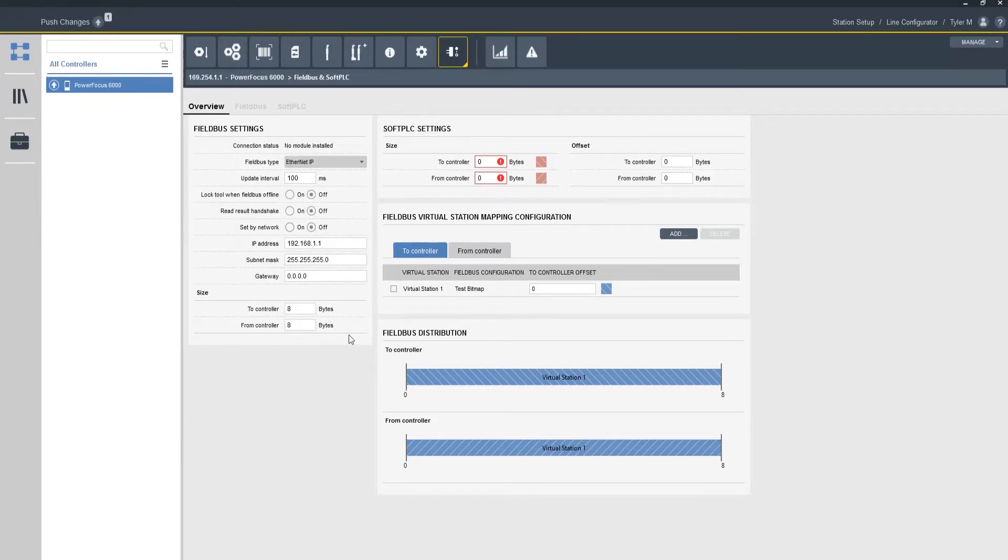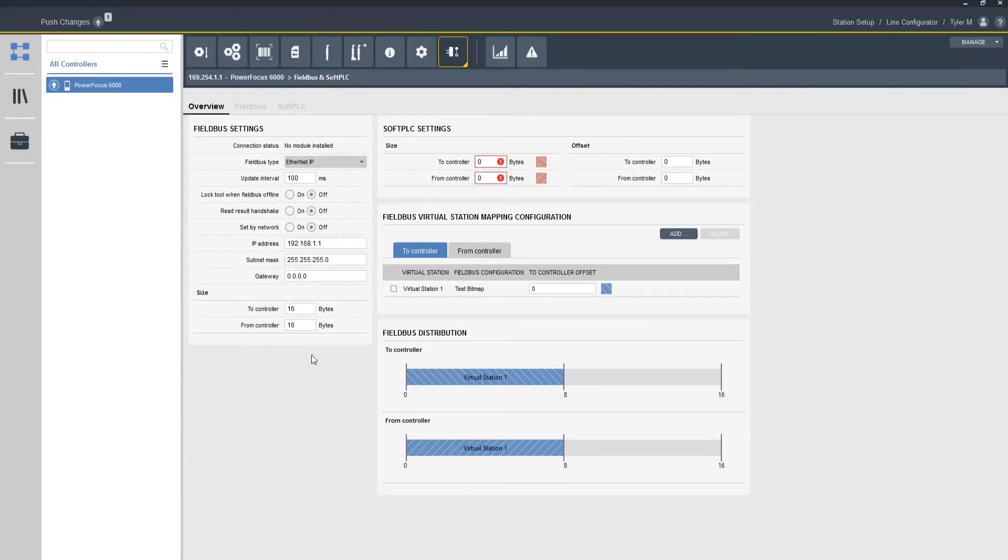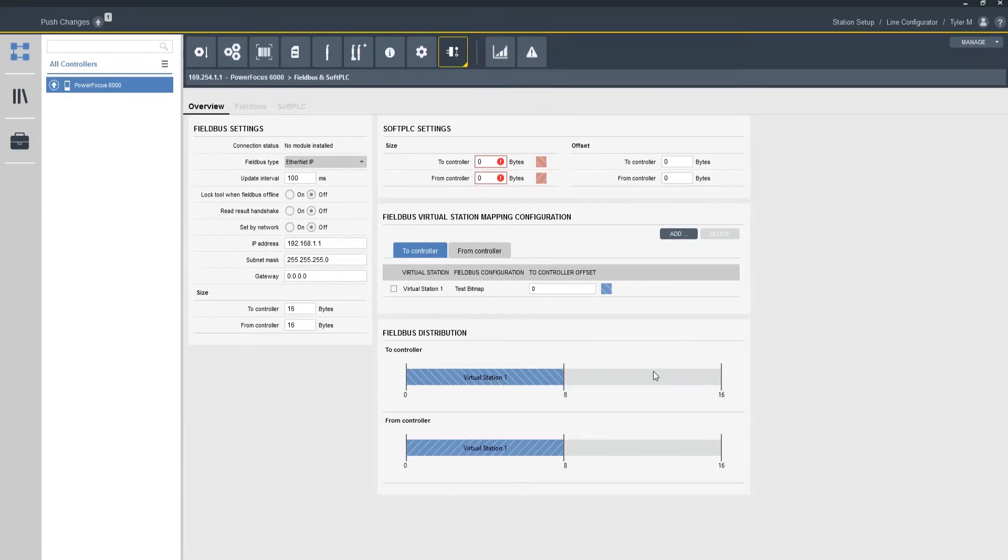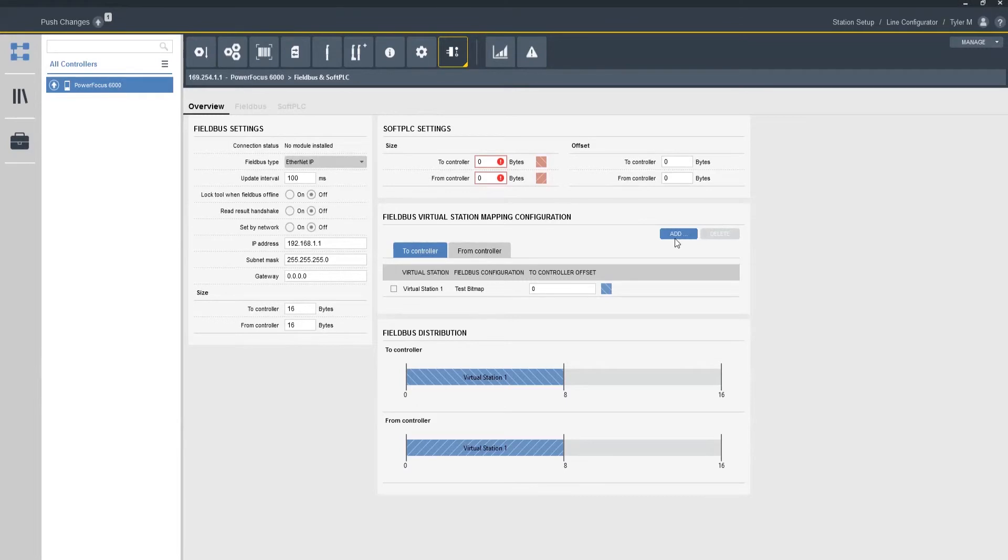Now obviously if I was to for instance maybe add a second tool you can see by changing the frame size it also gives us active feedback showing us a difference in size in the to and from controller for the field bus distribution. And if we were to click add and I had additional virtual stations I could have virtual station two in the second eight bytes in the bitmapping.